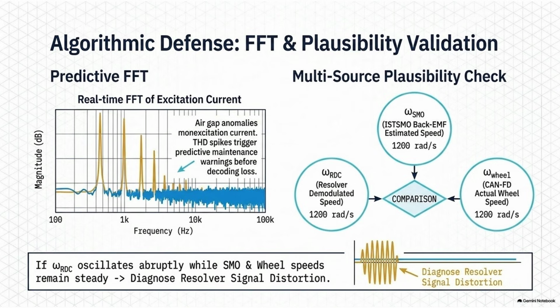And by running that FFT, the software can isolate that specific new hum. It calculates what is called the total harmonic distortion, or THD. Okay, so if the THD starts to slowly rise over time, the software can mathematically hear the physical mechanical wear of the bearing. That is incredible. It knows the bearing is failing before the driver feels a thing.